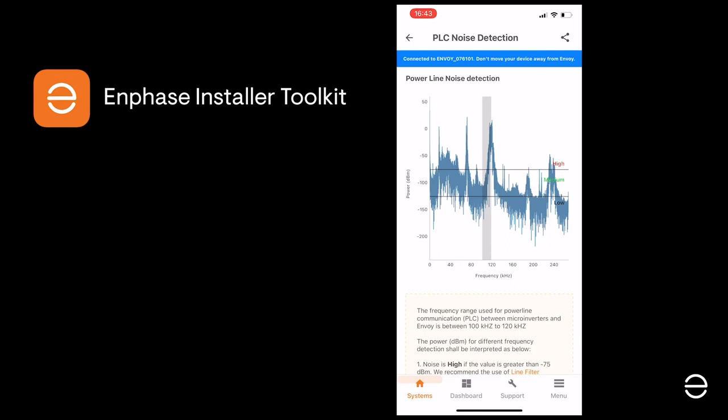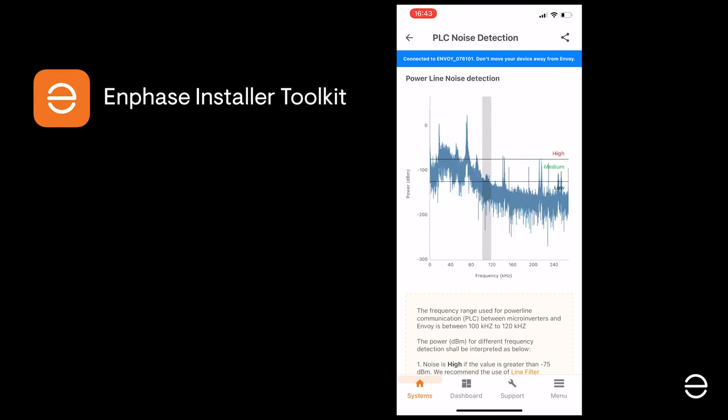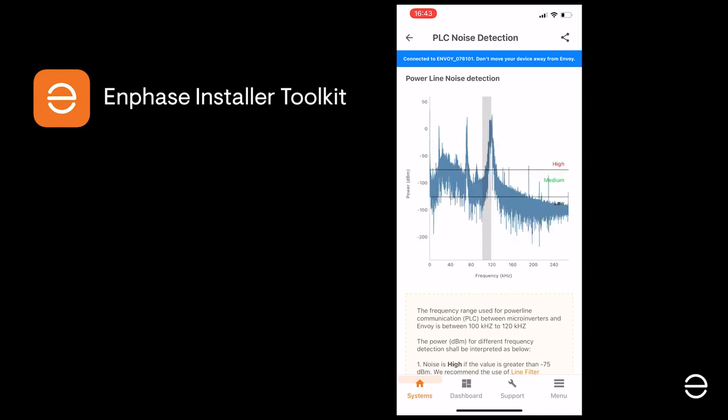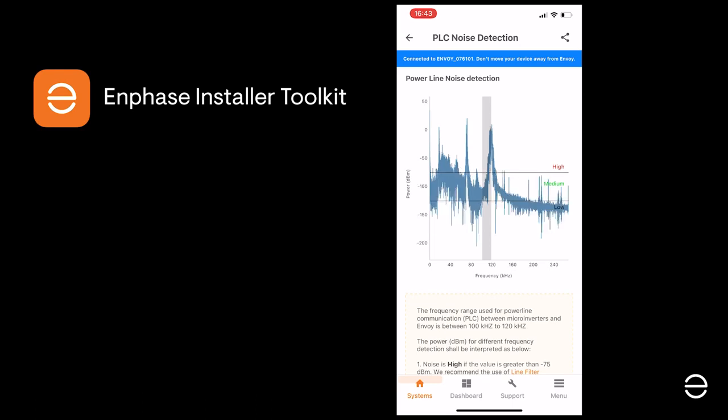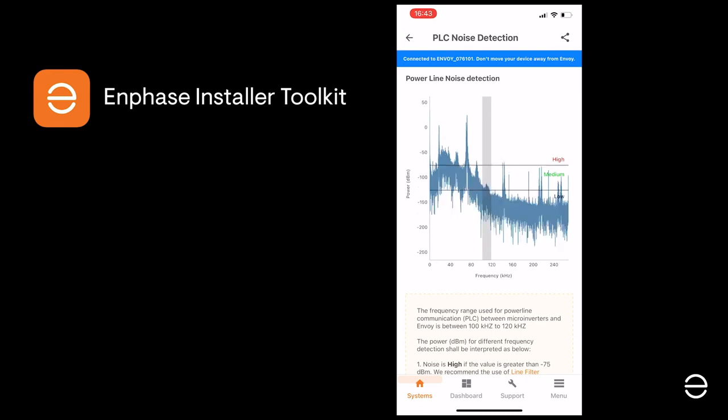You will see a real-time chart that displays all the communications on the installation, with a grey area indicating the frequencies used by Enphase to communicate with the various devices. The two horizontal lines will allow you to see the level of noise on Enphase communications.